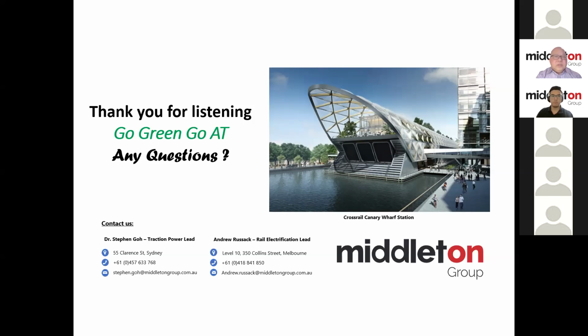So a good simulation must have all the gradient, all the station drive time, and your tractive effort curves for high voltage and low voltage control all in your model, including regenerative braking, to assess your system. Only when you have done that can you see whether some of this braking energy, when trains are going downhill, is being captured by a motoring train going uphill. So you should design it to maximize that energy.